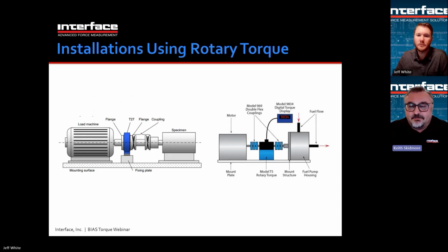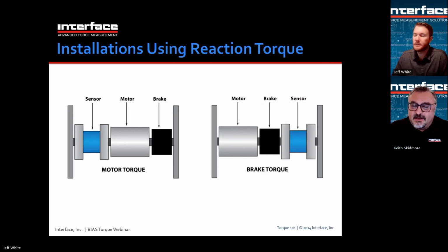Next slide, please. Oh, by the way, back up a slide. This conceptually is a great idea. In practice, it may be difficult to mount a motor or a brake to a torque sensor because of practical considerations. The motor housing may not have appropriate mounting holes. It might be a base mount that sits on a plate, for example. So this conceptually makes a lot of sense, but in practice, a lot of times these approaches don't work as well because of the fixturing requirements, and a rotary sensor would then be used instead. But conceptually, this works great. Next slide.